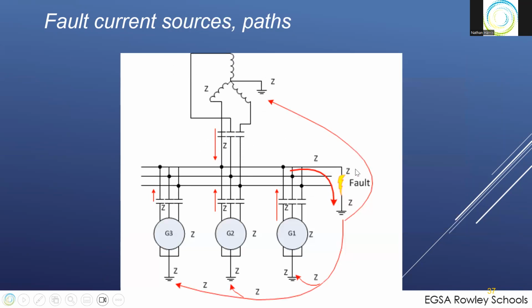A quick example of how a fault can do it. Let's say you have a fault in the switchgear, and Gen 1 is the closest, Gen 2 is further away, and Gen 3 is even farther away than that. You have the utility source in play as well. Of course, utility impedances are generally lower, so you get more fault current from a utility. Gen 1 is the closest, and so the impedance of its cable is the least.